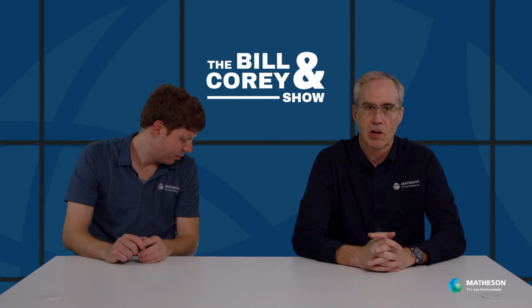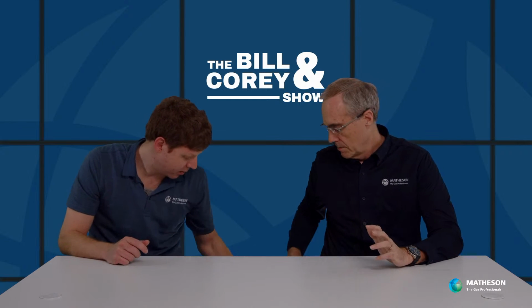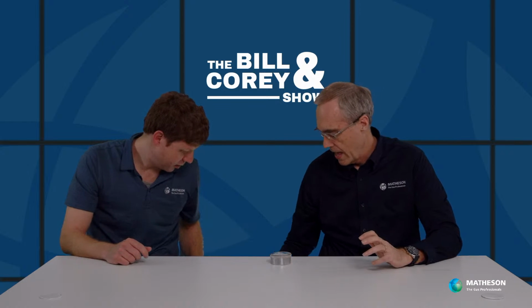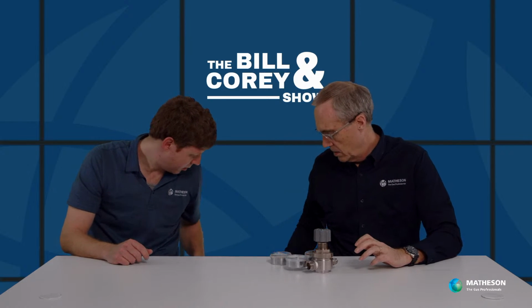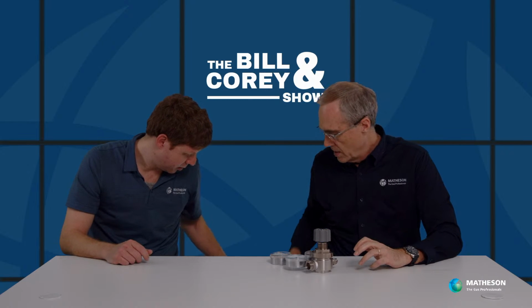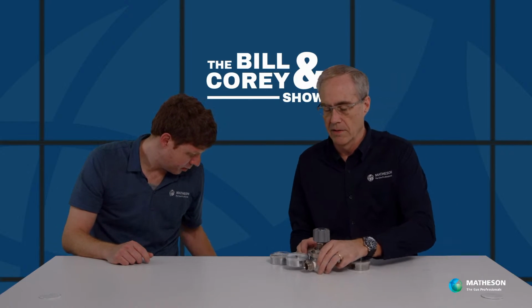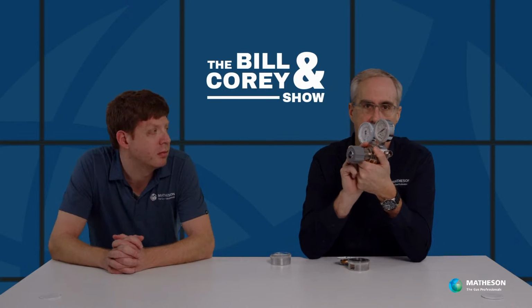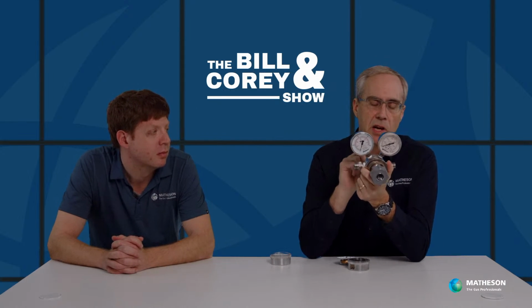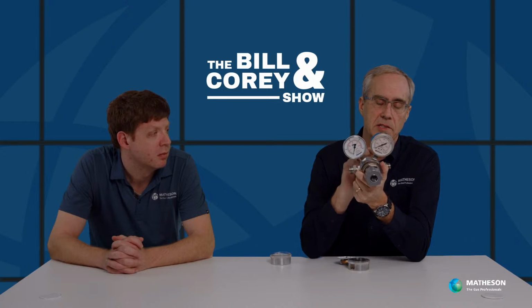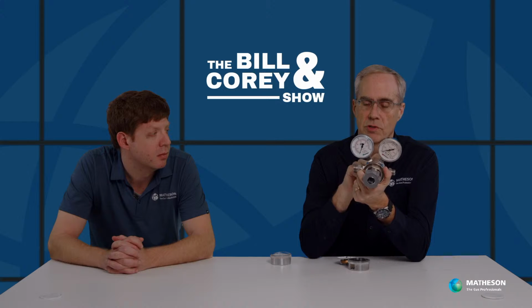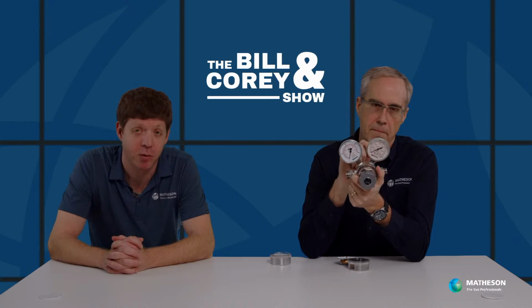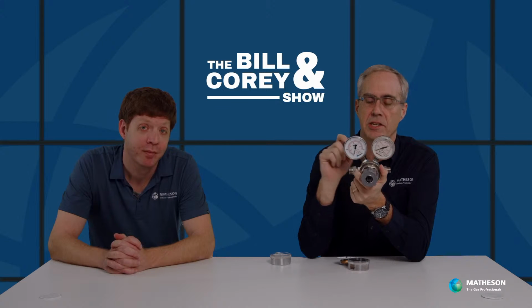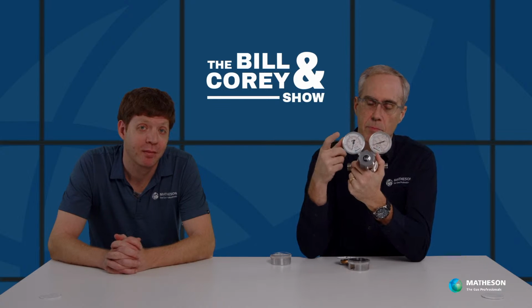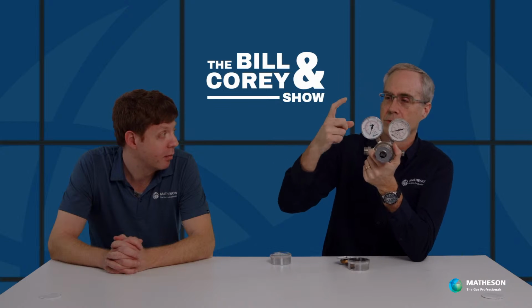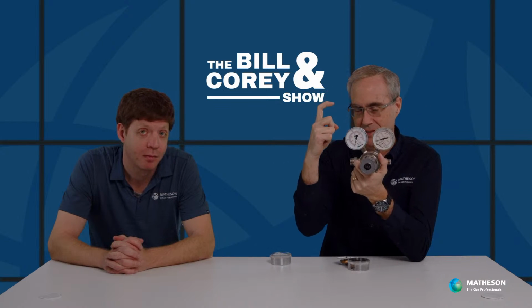So I want to talk a little bit about the regulator he has, and about pressure gauges and damages. The customer had our 3200 series regulator. It's a high flow regulator. Because it's a high flow regulator, it doesn't have an inlet filter, so these are more susceptible to creep leakage. And what happened was, the delivery pressure gauge needle was bent. It was bent like this, which is kind of funny.